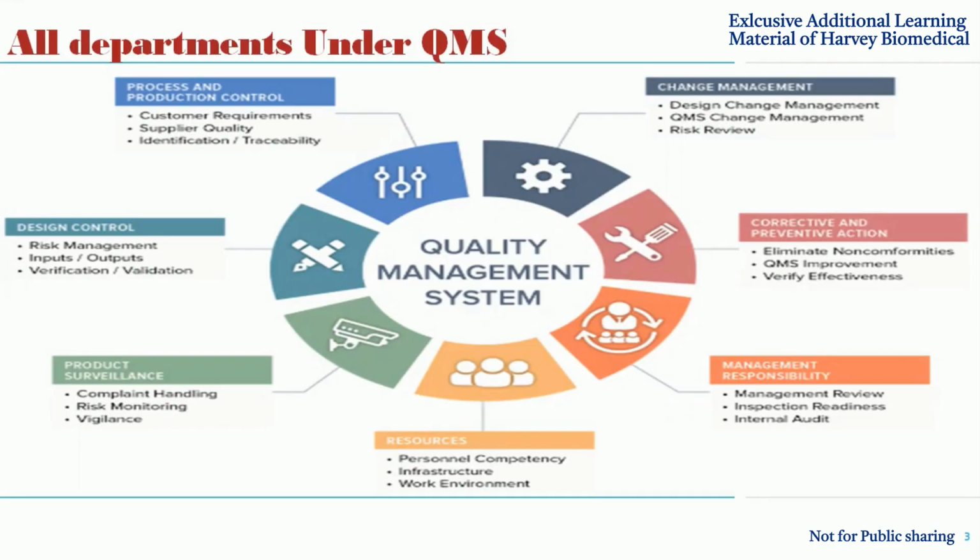were received by the manufacturer because performance was reduced. Then they immediately upgraded to the next software. You see, they did not validate properly, and they concentrated on only one non-conformity, but did not verify the consequences. That's the reason we have to check the effectiveness of the specific upgrade, software, or changes with respect to the devices in the market.